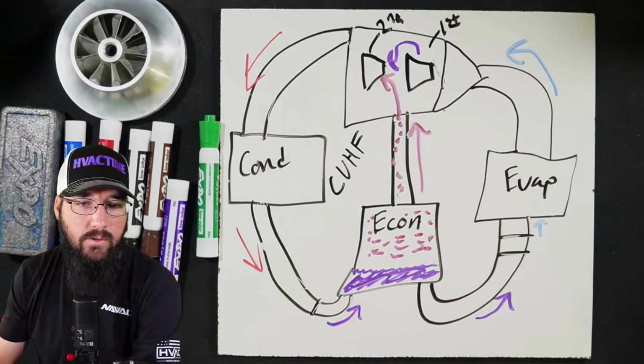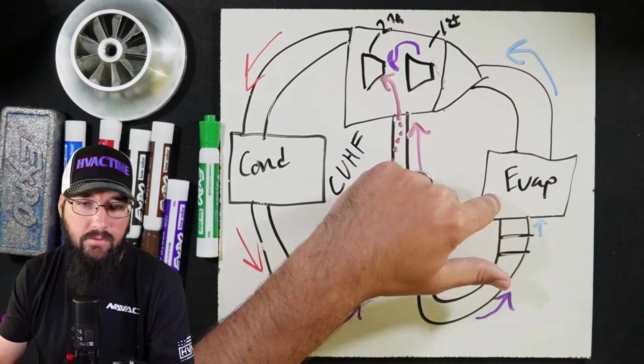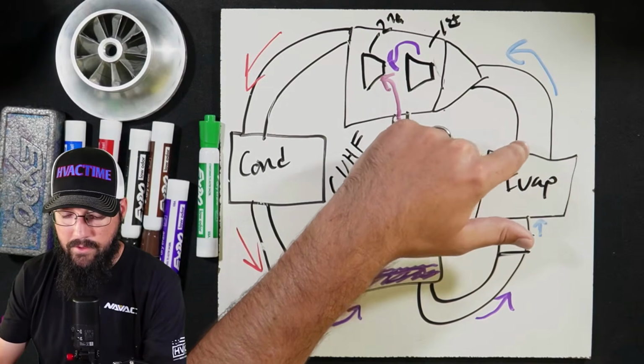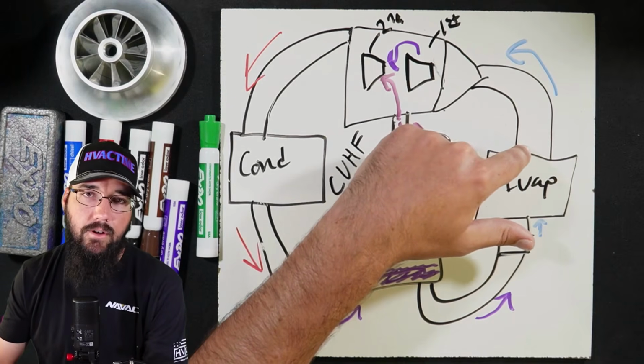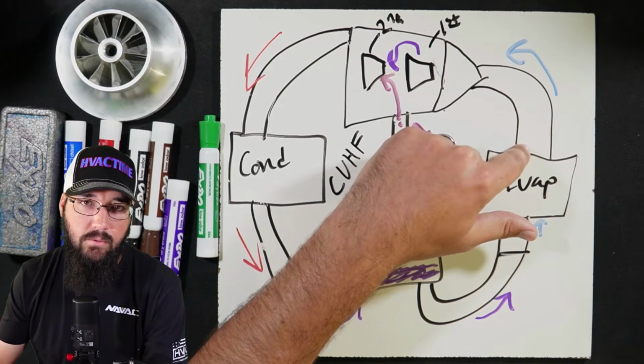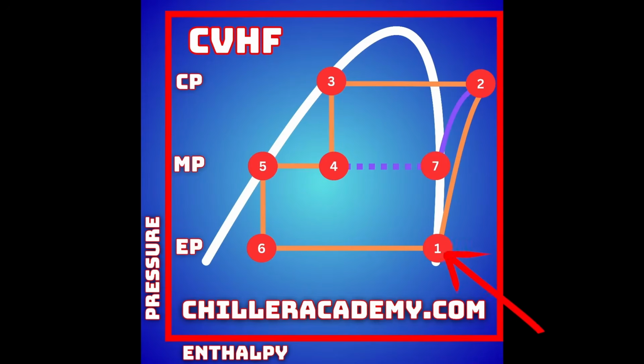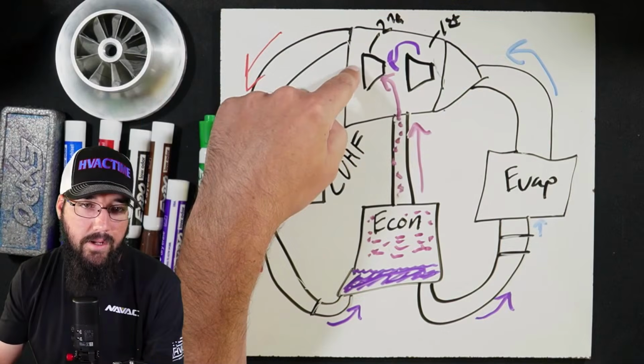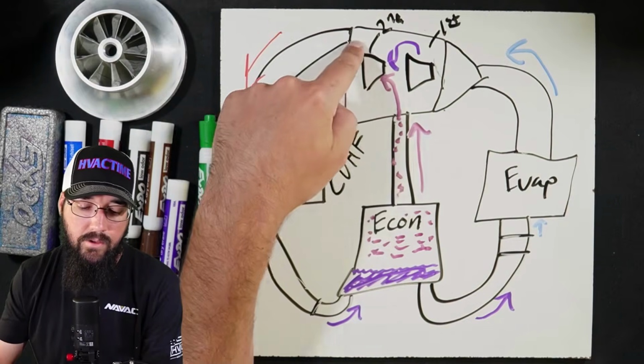So on point number 1, we are right here in the evaporator. We've gotten into the evaporator. We're actually here at the suction line, and we're returning back to the compressor. So this is point number 1. As we go from point 1 and we've entered the suction of the compressor, up right here we are at the compressor discharge. We have raised the refrigerant pressure, and we have raised its saturation. From here, we have now gone through the compressor, and we're back over here. So this was our point 1. Over here would be our point 2.